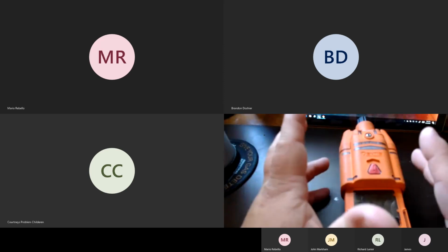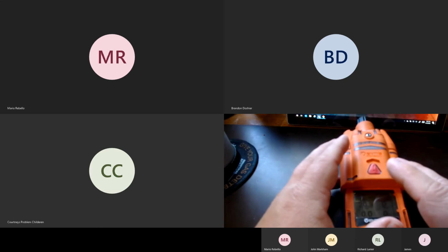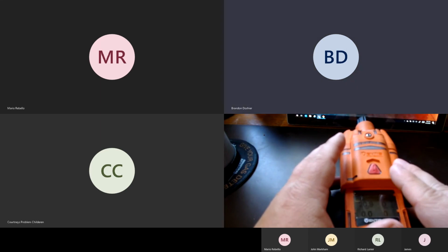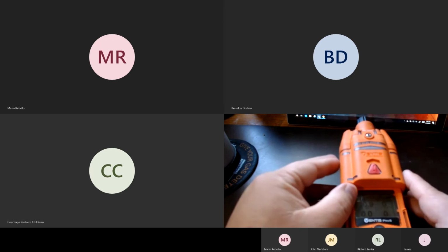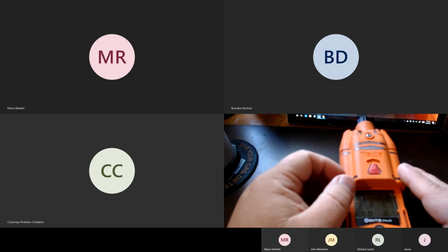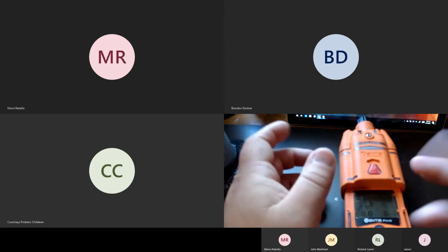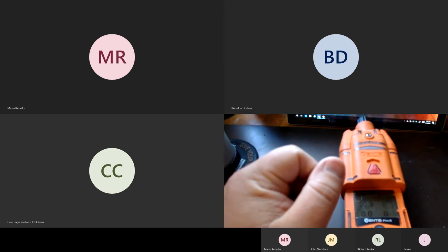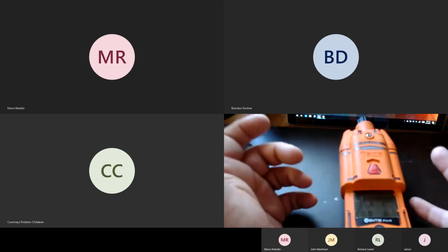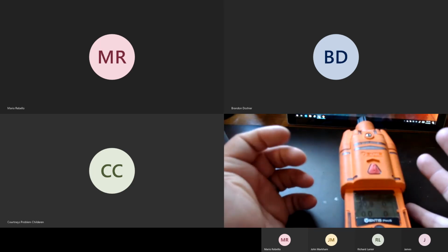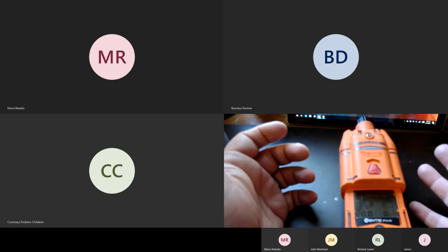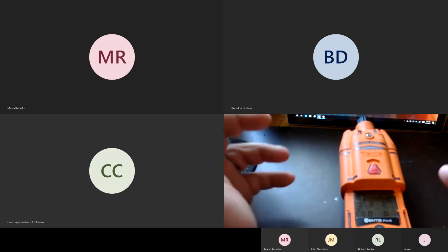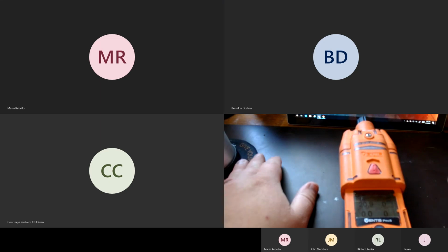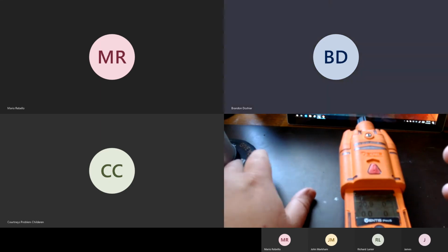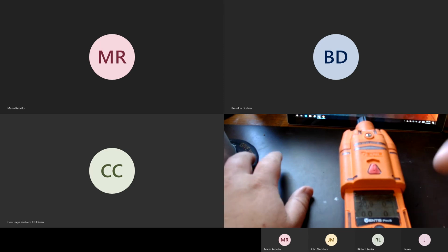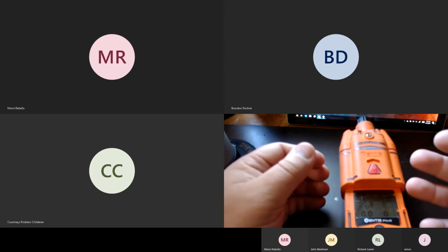Now, these instruments that you got them for, are they basically going to be overhaul instruments and CO alarms? Mostly, yes. Okay. So my recommendation on that would be to actually, and I'll show you in the settings, probably go in and shut off the TWA. To shut it off, though, you actually have to just crank it up as high as it will possibly go. The reason being is CO calls and overhaul, the whole purpose is you're still wearing your SCBA until the levels come down low enough that you can take it off. So that's the reason why TWAs really don't matter, because all those readings that you're getting where it's in the high levels, you're still under air.